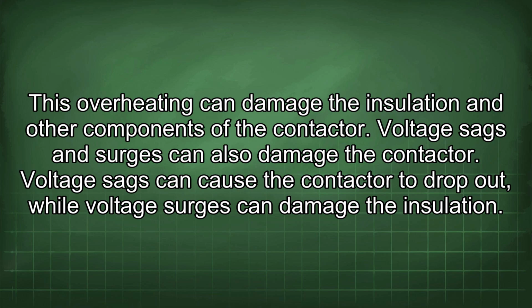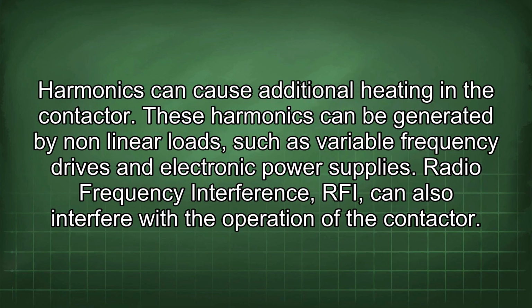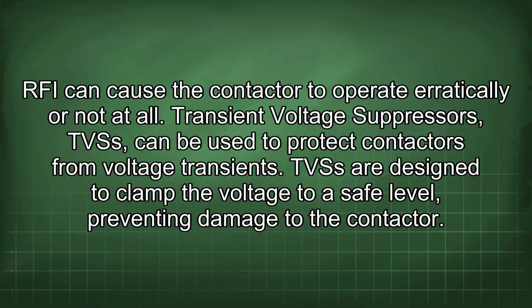Voltage sags and surges can also damage the contactor. Voltage sags can cause the contactor to drop out, while voltage surges can damage the insulation. Harmonics can cause additional heating in the contactor. These harmonics can be generated by nonlinear loads, such as variable frequency drives and electronic power supplies. Radio frequency interference (RFI) can also interfere with the operation of the contactor. RFI can cause the contactor to operate erratically or not at all.